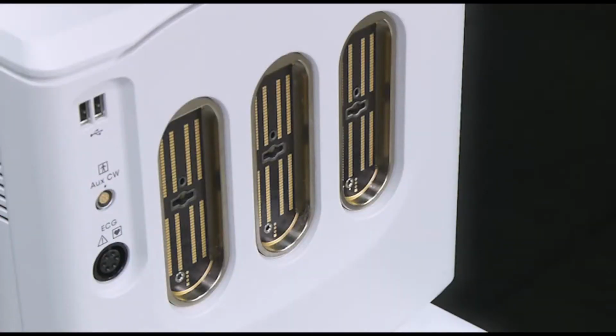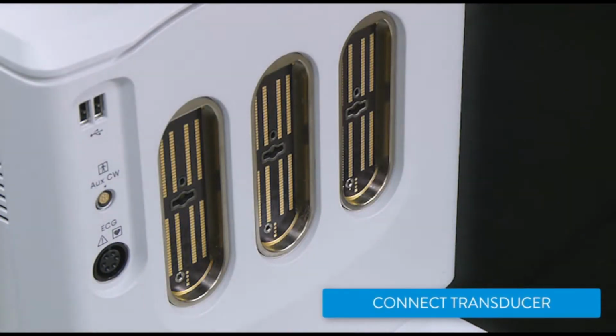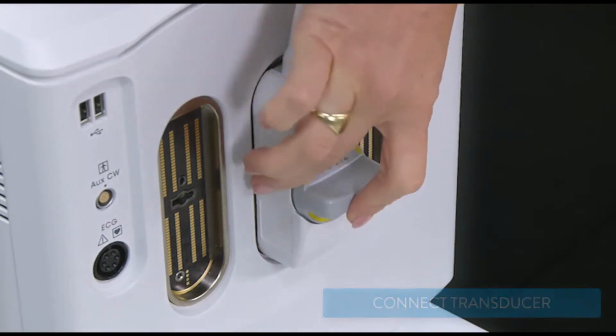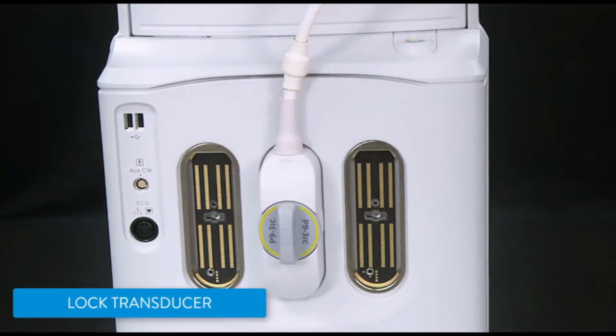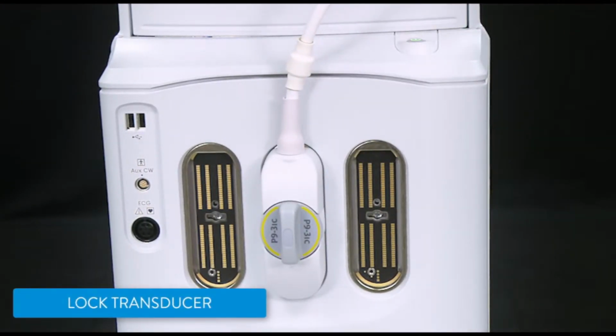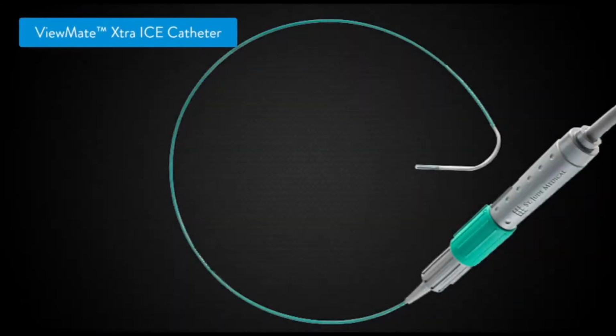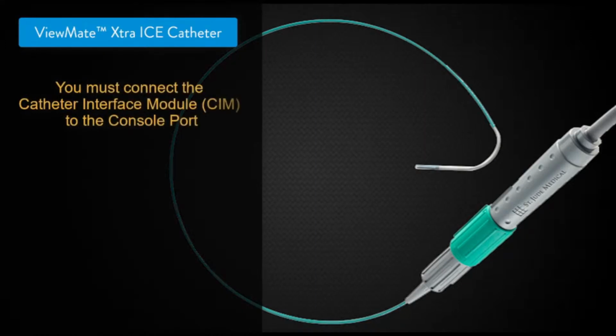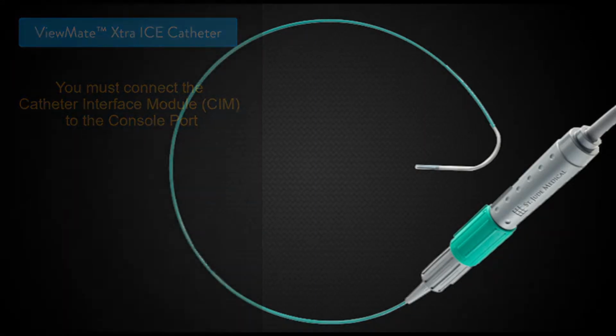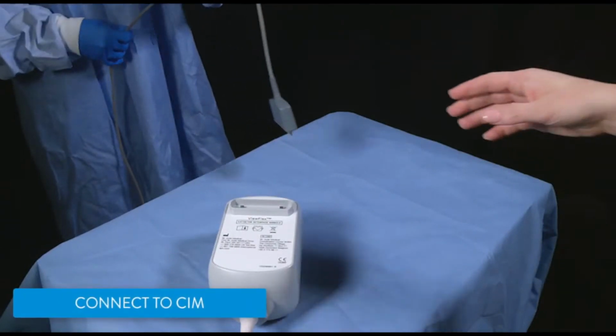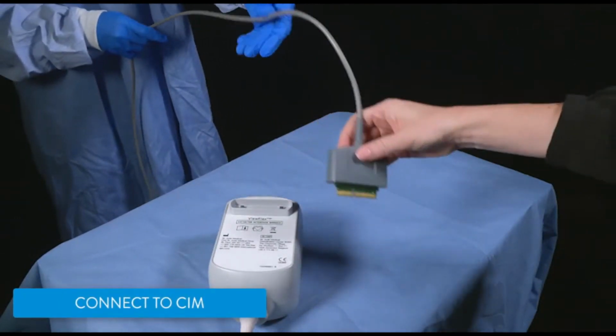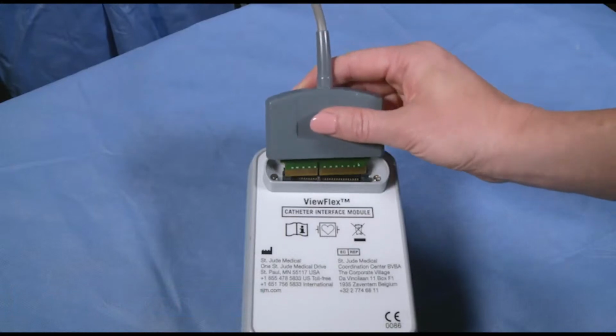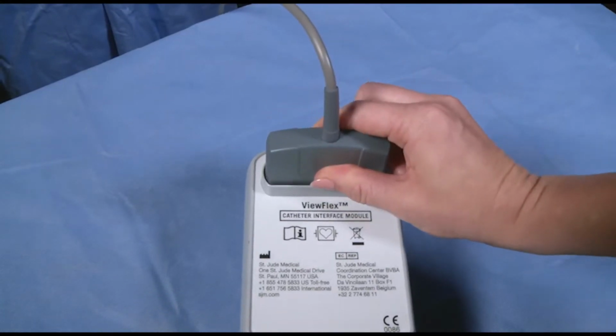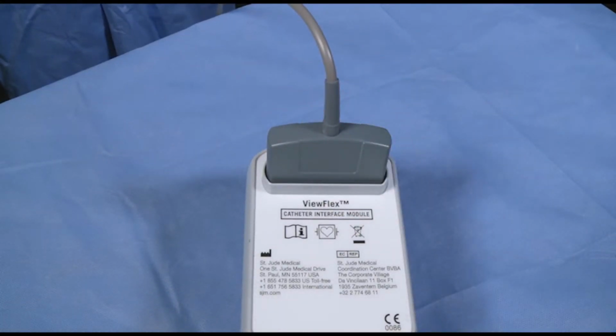To begin imaging, connect the selected transducer so that the cable is oriented upward. Rotate the connector locking knob clockwise to lock the connector into the port. For the ViewFlex Xtra ICE catheter, there are 2 connections. You must connect the catheter interface module, or CIM, to the console port. Once the connector portion of the catheter is handed off from the sterile field, orient the short and long sections of the connector and plug the catheter connector into the catheter port.